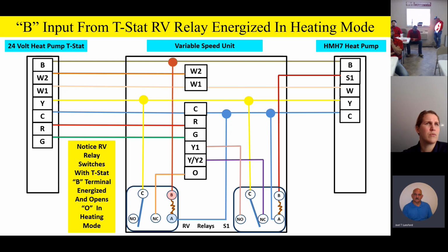We're talking indoor unit only now. The O terminal has two functions. Number one, it tells the indoor unit that it's in the cooling mode. In addition, if the O signal is broken and I'm in the heating mode, it disables the cooling on delay ramping profile for humidity control and so on. So some of these advanced features on the indoor unit are driven by the O terminal on the indoor unit.